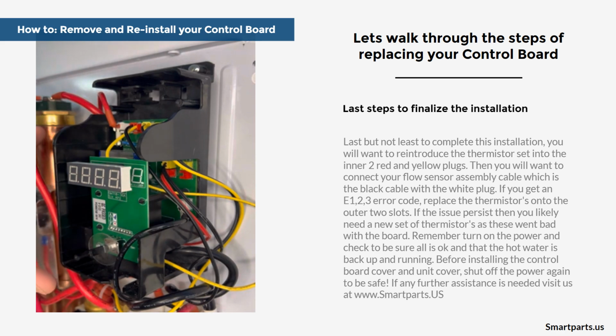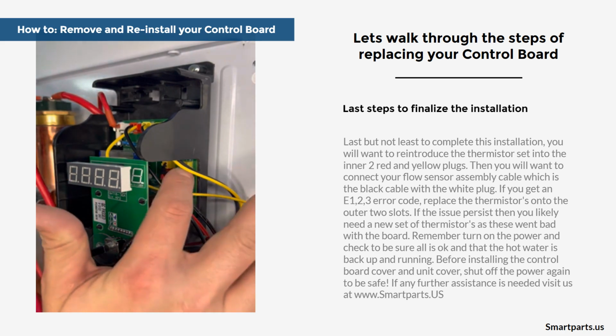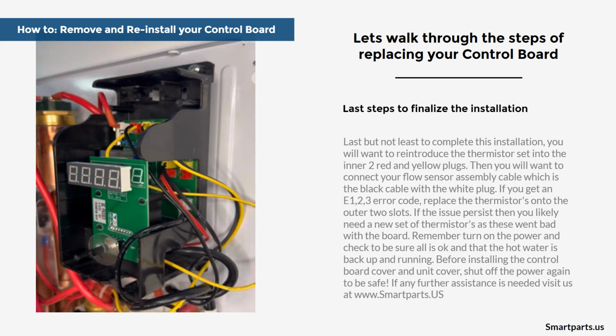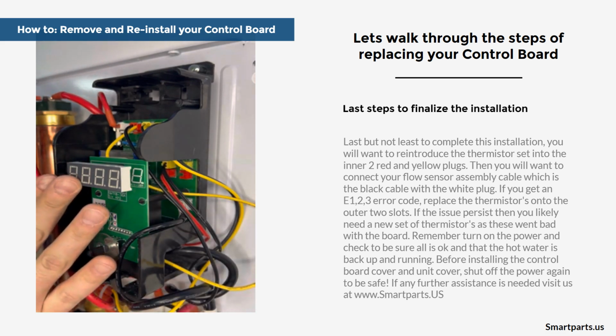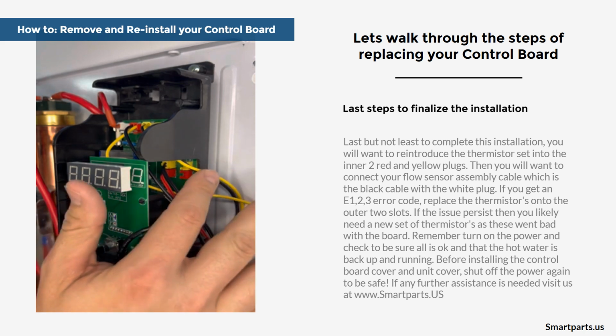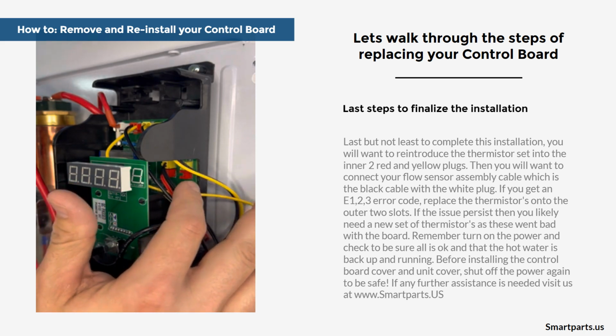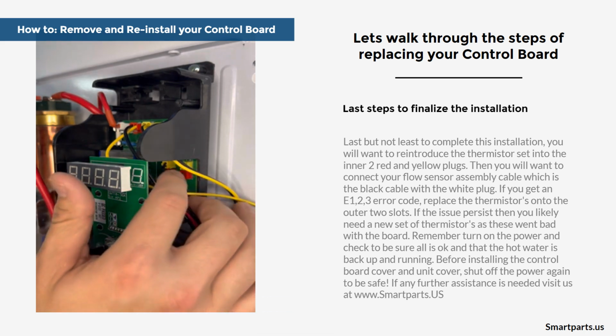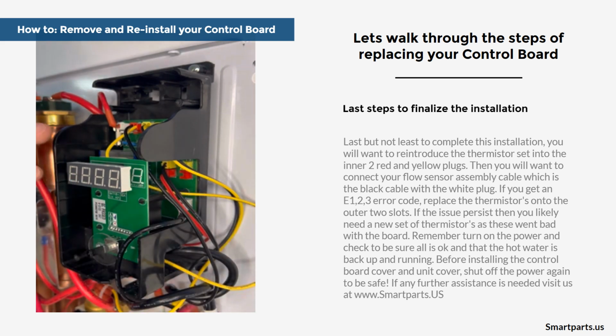Now, when you turn this unit back on, if you get an error code for your thermistors, you can test it on the outer two and do the test again to see if the error code goes away. If it doesn't go away on either the outside or the inside, chances are your thermistors went bad when your control board went bad. So with that being said, we've now completed the installation for your control board.